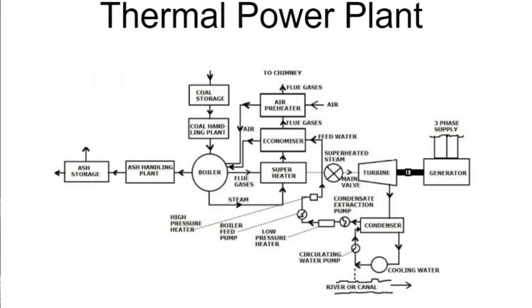When the plant is not working, the generator and turbine cannot simply be stopped completely. A small amount of heat or steam is provided to keep them in running condition. This is called the turning gear — the turbine and generator shaft must always be kept slowly rotating. Otherwise, the shaft — which can weigh 100 to 200 tonnes — will bend under its own weight, causing deformation.